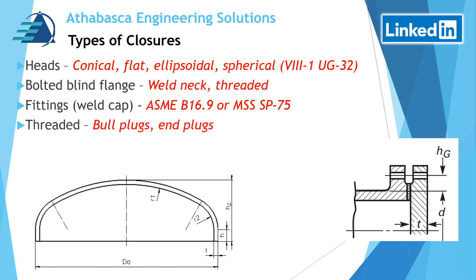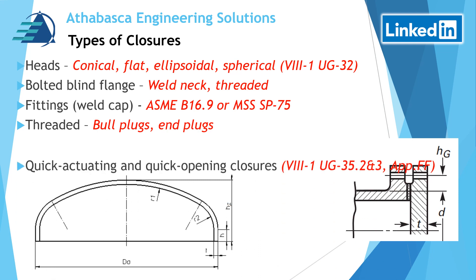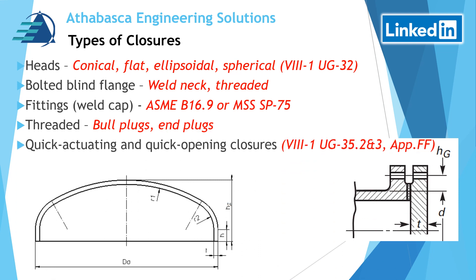Next, we have threaded plugs. And lastly, the Boiler Pressure Vessel Code ASME Section Eight, Division One breaks closures into two categories of quick actuating, found in UG35.2, and quick opening, found in UG35.3. It also mentions that documentation is required for those types of closures, and the quick opening closures guidance is found in Appendix FF.